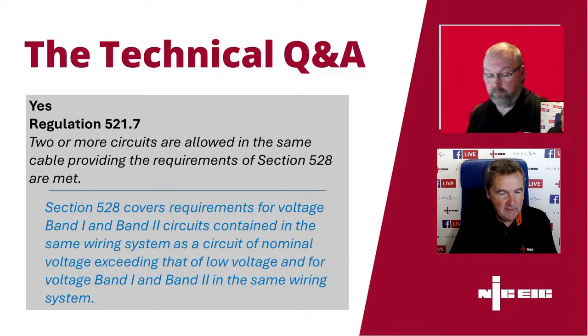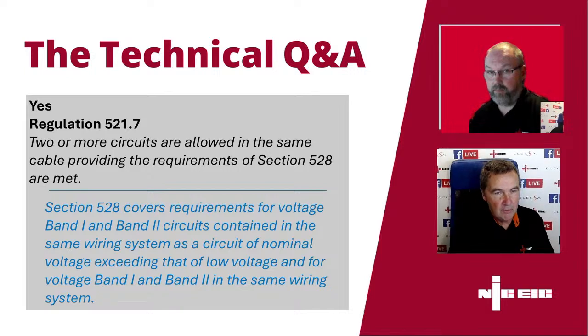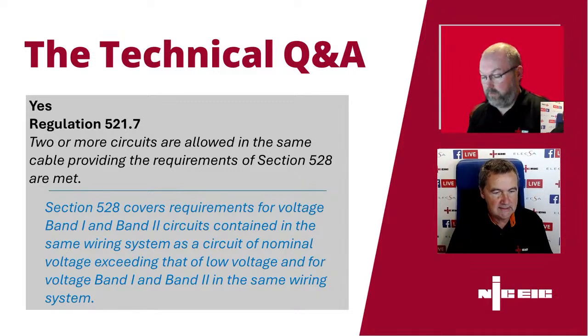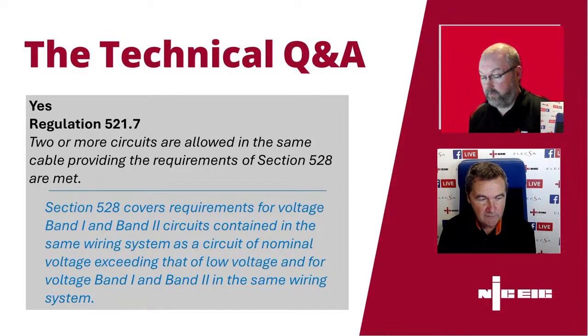There is a reference though that you have to meet the requirements of section 528, and section 528's got a number of requirements, most importantly around the fact that when you're dealing with different voltage bands, the cables in a multi-core cable all have to be capable of, their insulation must be rated for the highest voltages available. So that's one real strong consideration. But generally, if that's done, then it's perfectly acceptable. So you need to comply with the requirements of section 528. But as Craig said, 521.7 nice and clear tells us that two or more circuits are allowed in the same cable.